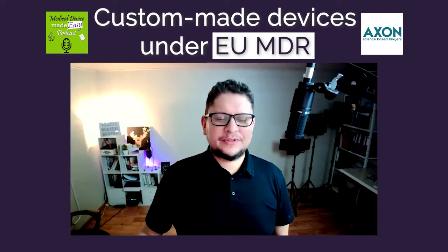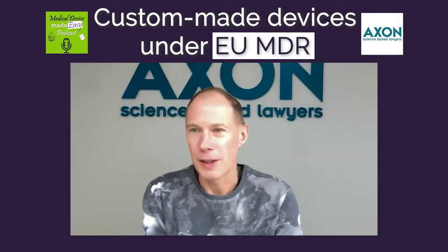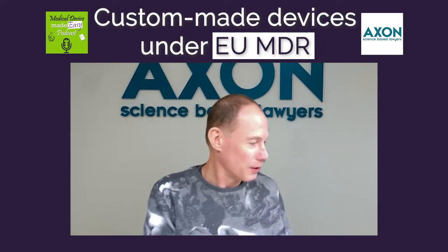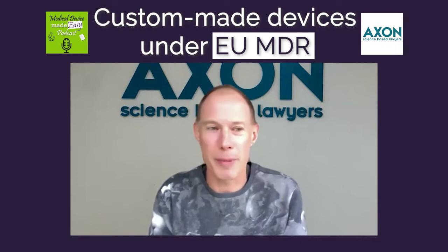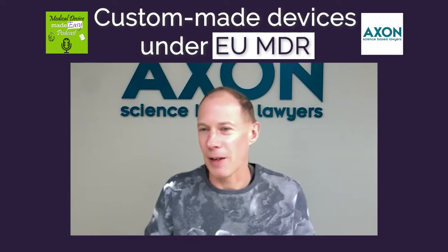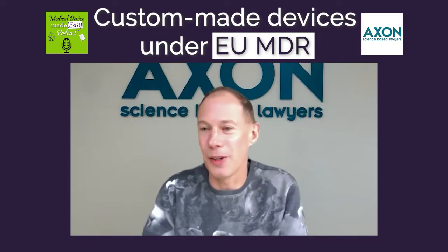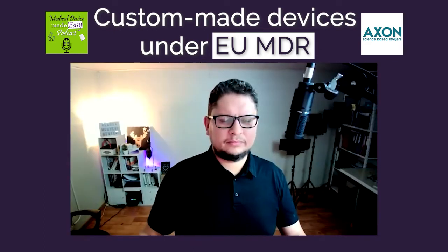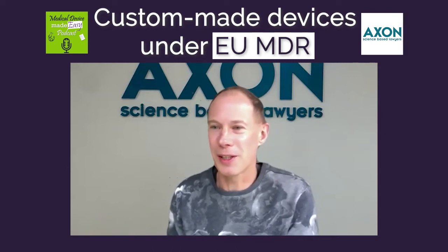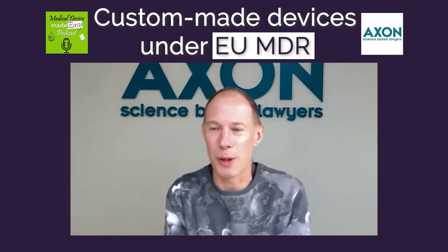So can we say that those three products are custom-made devices, or some of them are not at all? No, it's basically the really patient-specific ones that are the ones that are custom-made devices, because they are made for this person specifically, whereas patient-matched ones are related to this patient in the sense that dimensions are related to the patient, but they're not necessarily made for this patient specifically. Okay. Basically, as I've called it in an old blog post of mine, it's like in-process customization. So you customize something in the production process, but it doesn't mean that it's a unique product for a unique person. It's basically just tweaking production parameters during the production process.